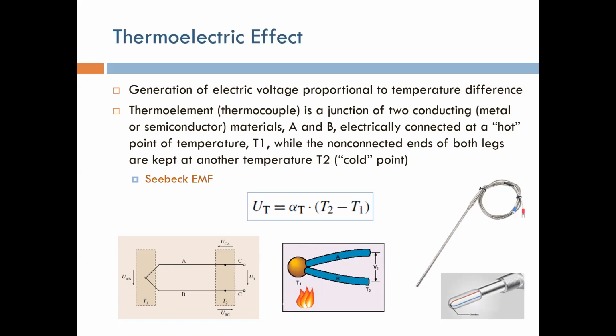Such sensors look something like this — these are examples of practical thermocouples. The junction is somewhere here, with a long wire so you can take it far away from the furnace or high-temperature source you're measuring. The reference temperature is taken between these two terminals, where you measure the voltage and use the equation. You usually get the constant from the data sheet and the reference temperature from another sensor, then compute T2 based on the voltage measurement.